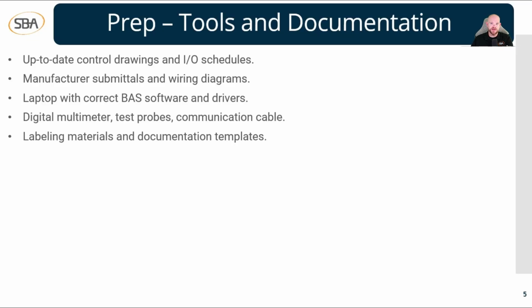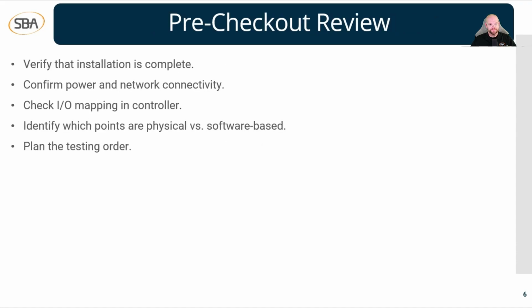Create a note section on one side of it so that you can put any notes. If there's a problem and you can't check it off because it's not good, then put some notes. Or if something was wrong and you had to fix it, put the note in there like, hey, this didn't work at first, but we went through, troubleshot, and found an issue with our wiring. We changed the wiring and now it's working. These templates are a great way for you and your team to stay focused on task and together, teamwork wise, throughout the whole point-to-point checkout process. So make sure you have plenty of labeling materials and create these templates if you can. It just makes everything way easier on you and your team, and it's just way more streamlined in my opinion.